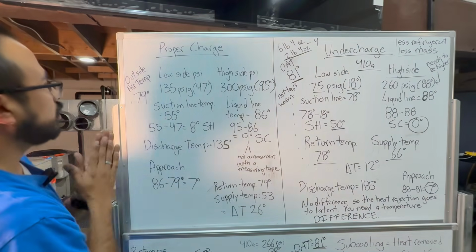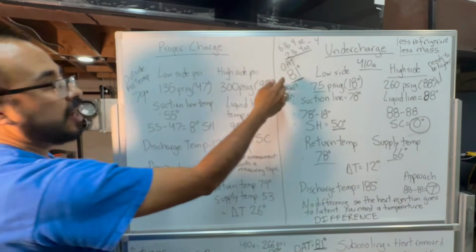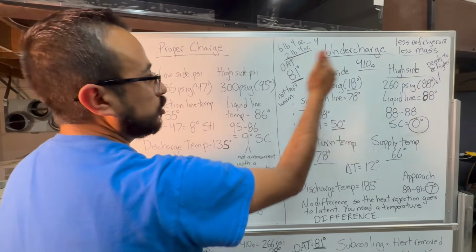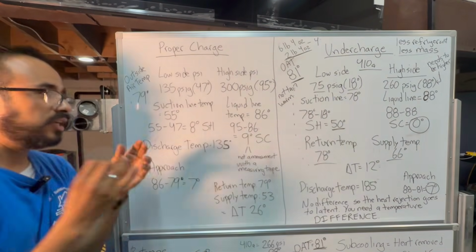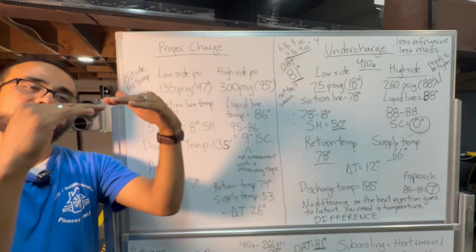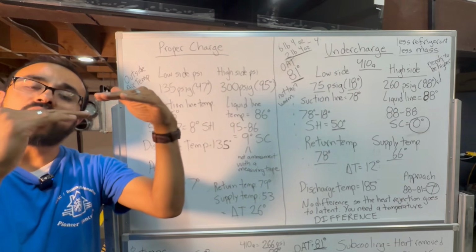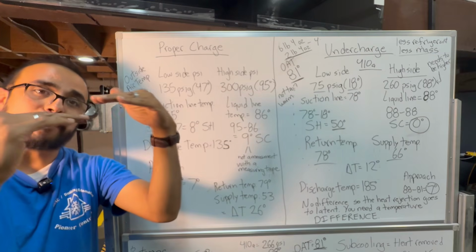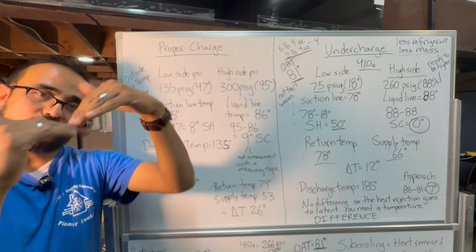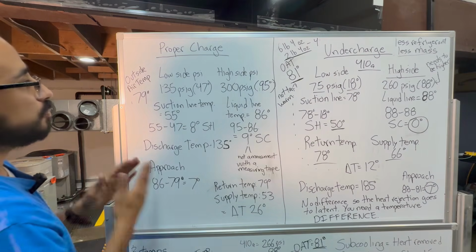It's about, what is it, 16-degree difference. On this one, from the condensing temperature to my ambient, only 7. So here, over there on that one, I had about this much. On the properly charged system, more of a difference in temperature. So I can reject more. So that is why it was working fine, because look at my numbers.